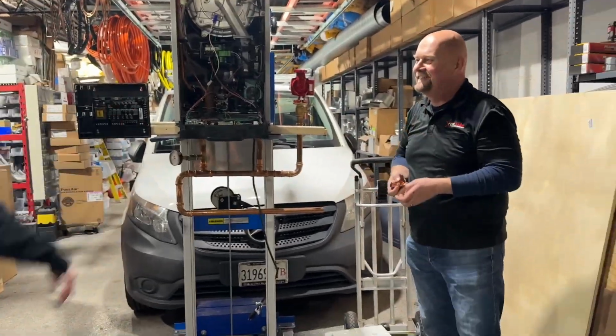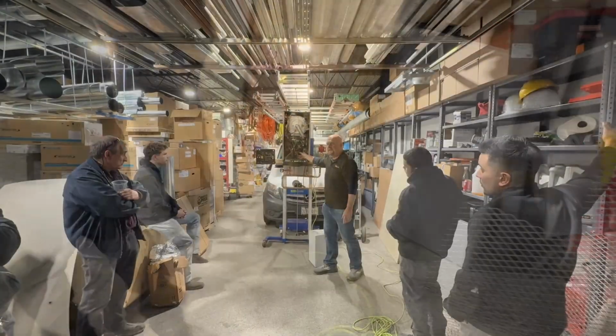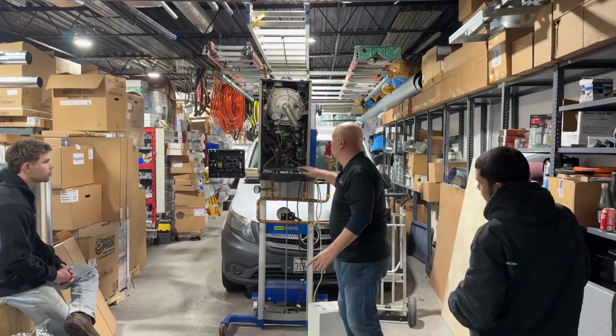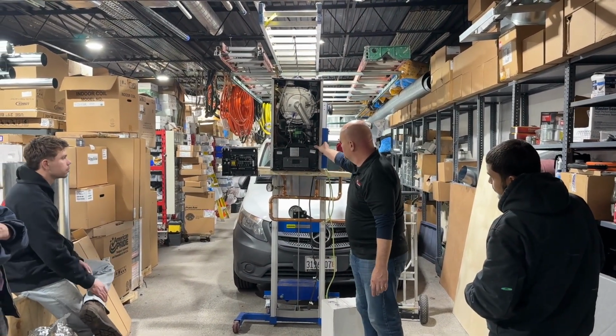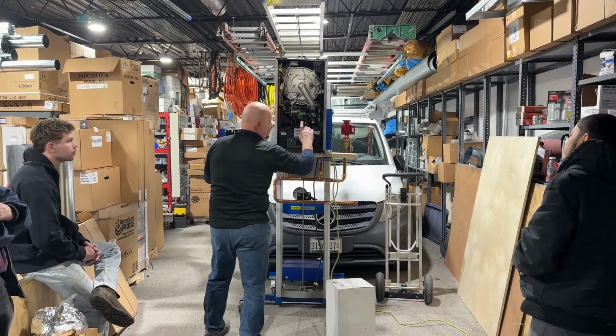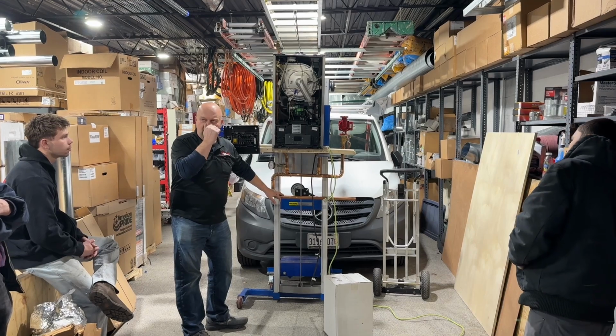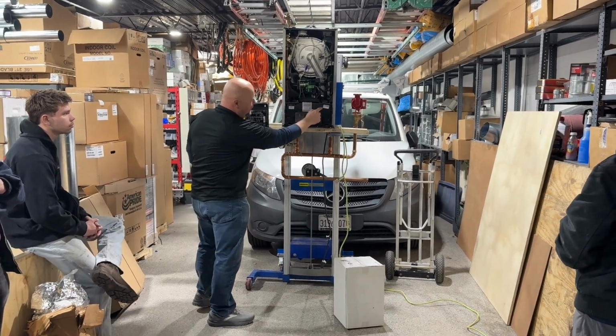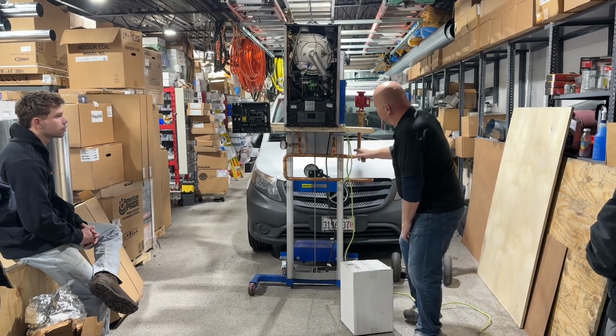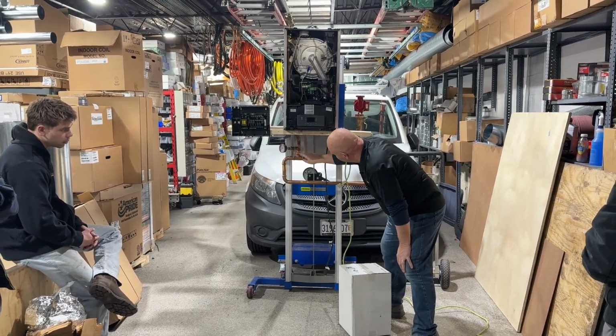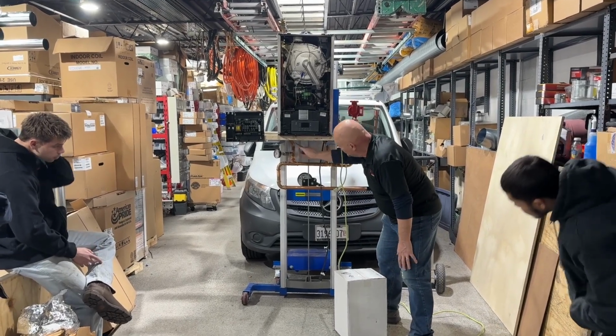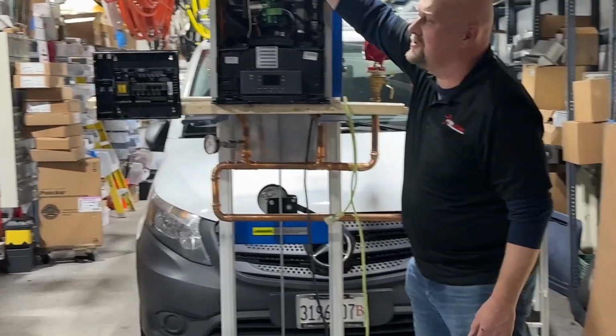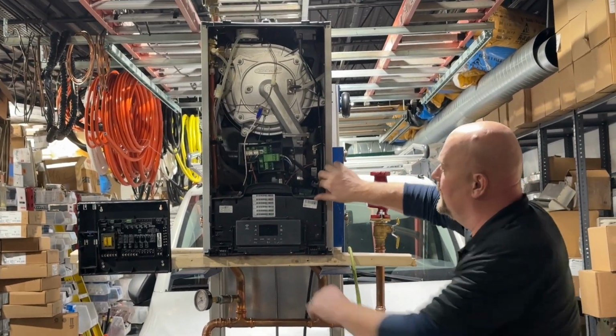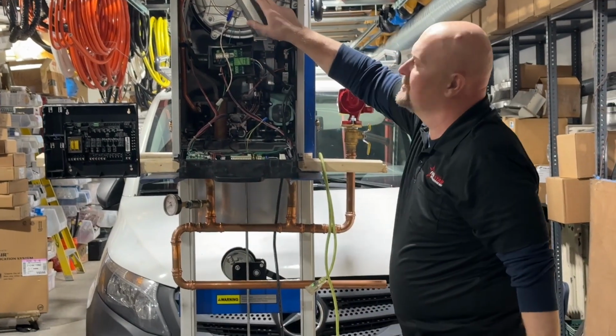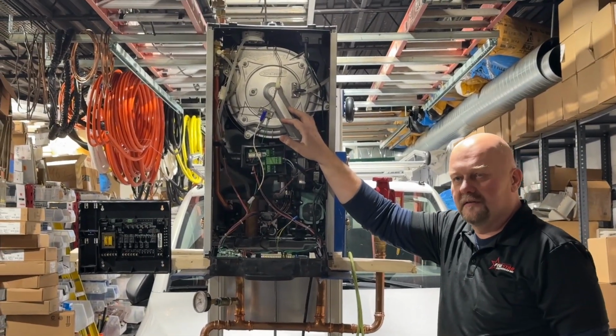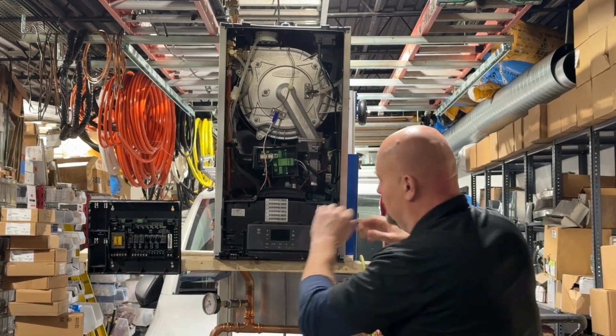Yeah. Oh man. This is a boiler pump. All right. So I'm going to put it back up so you can see better. Okay. Whenever this boiler is engaged, whether it's to heat the house or provide hot water for domestic hot water, that pump is on. What that pump will do is circulate the water through this circuit. You guys see this circuit? This is a circle. It goes through the heat exchanger and keeps circulating. That is the only function of this pump, to keep the water flowing through the heat exchanger so the heat exchanger doesn't overheat. Now, this will provide no heat to the house at all.